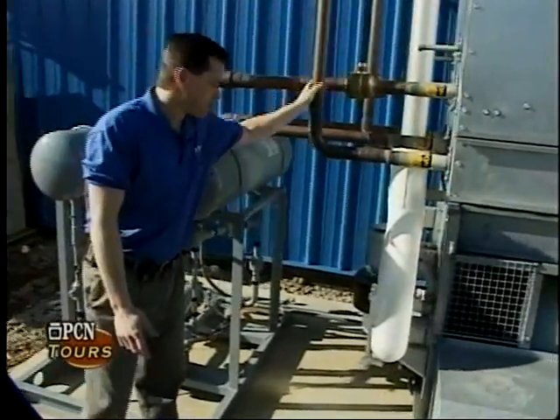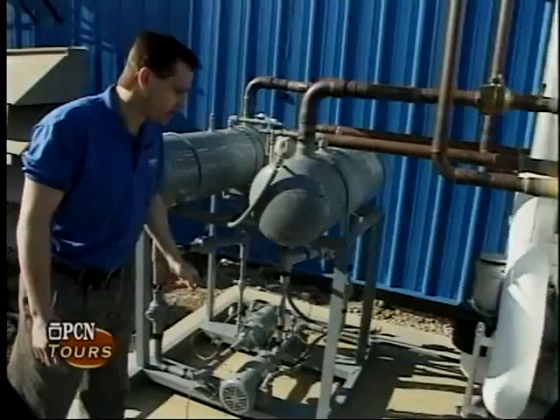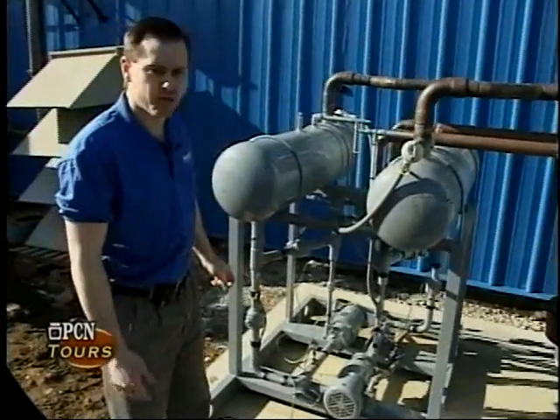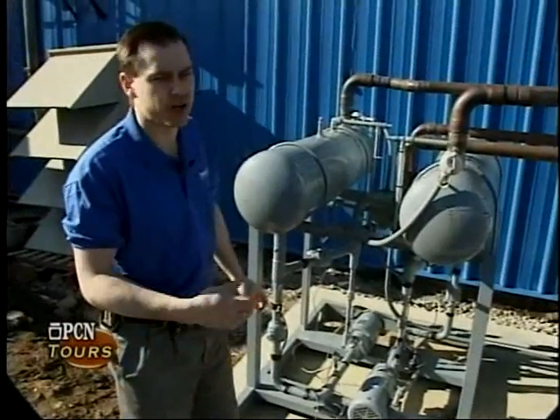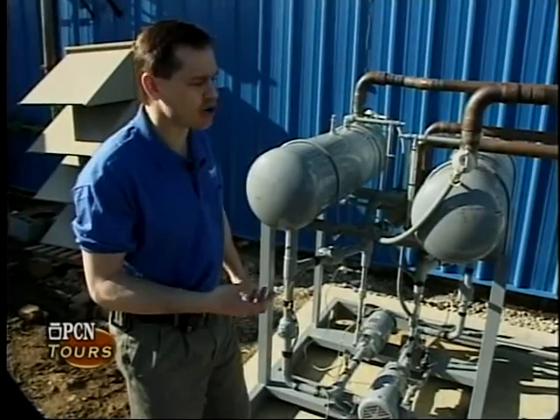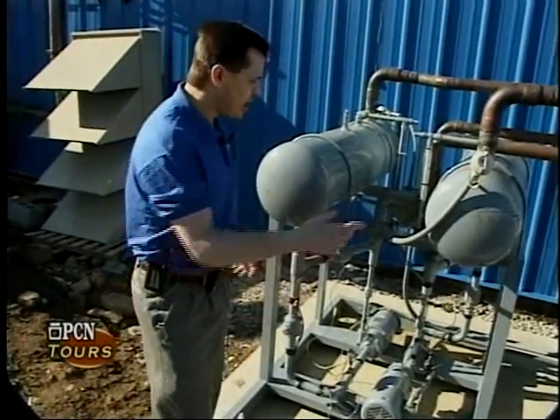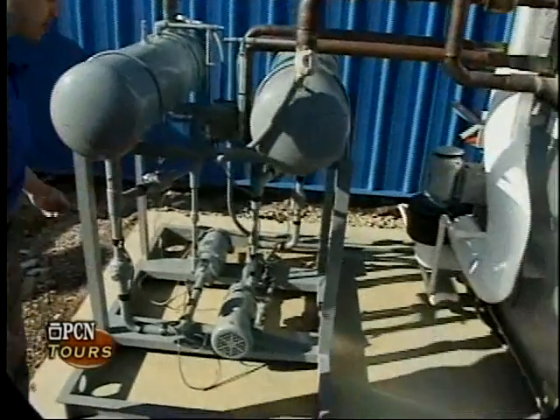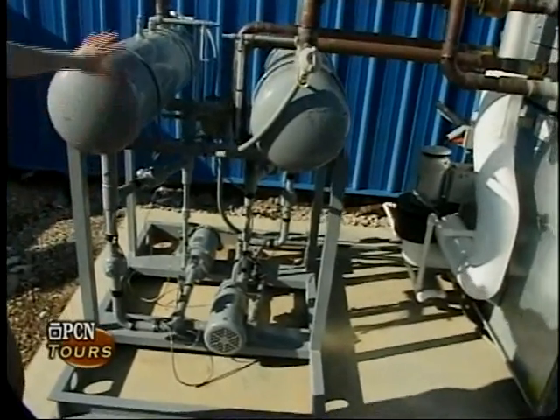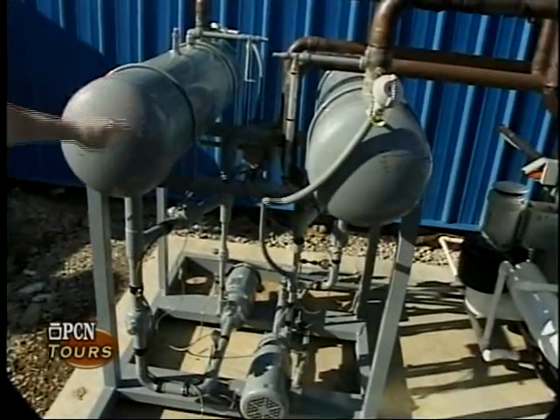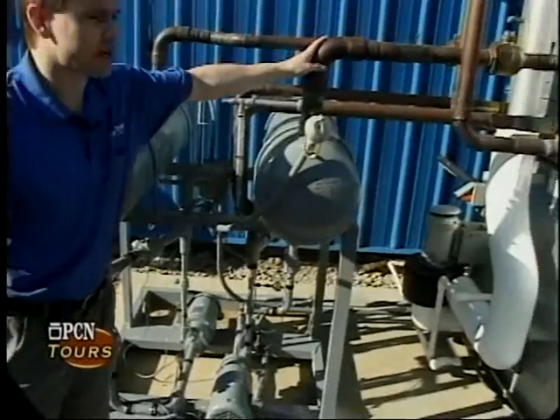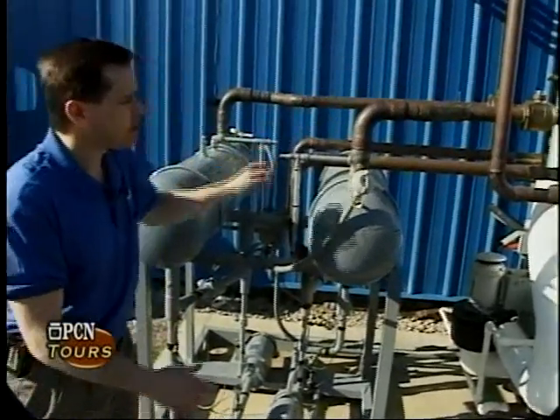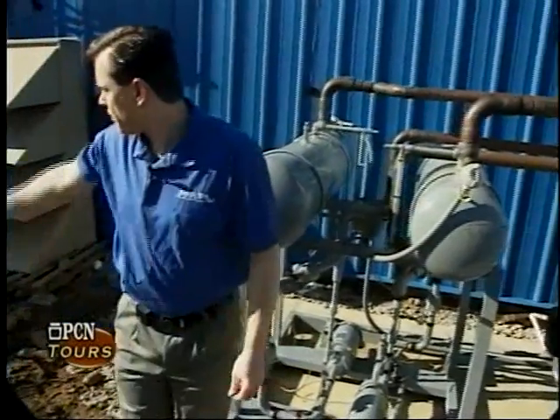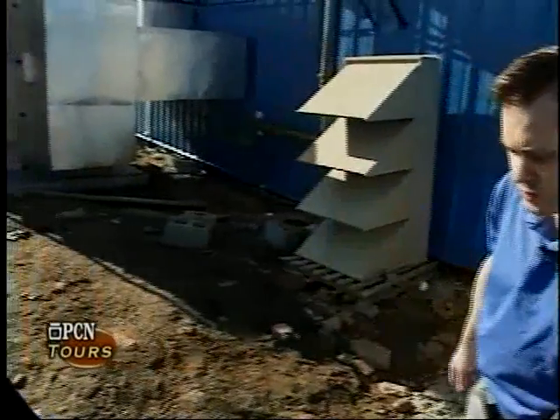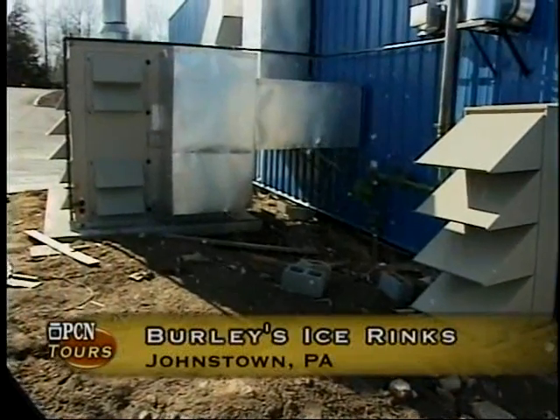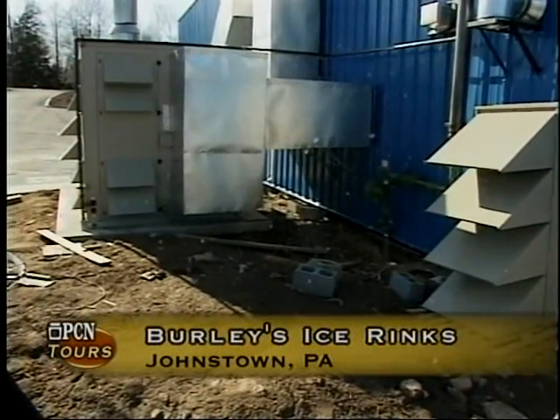Basically the whole process of the refrigeration system is a physical change of the refrigerant, changing it from a liquid to a gas and then compressing it back to a high pressure gas, cooling it, and it comes back to a liquid. This is also another skid that we manufacture as a company. These are our LPR pumps and our receiver skid. And this is the field piping work that's done in the field. Everything else is skid mounted. Then we also have, shown over here, a dehumidification system, which is very important for an ice rink, which is also manufactured by our company.